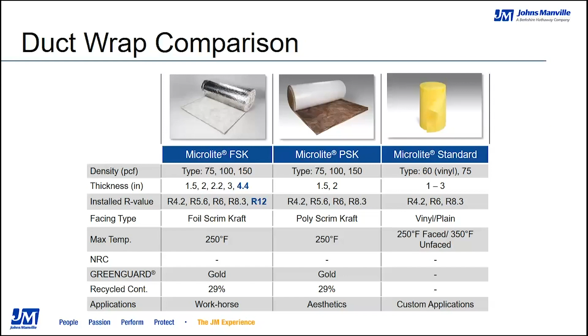So looking at duct wrap installation, the first thing I want to draw your attention to is over on the right-hand side of the screen, and just give you the components of actual duct wrap. This is an actual roll of Microlite FSK duct wrap, and you can see that the fiberglass is the white color there. The foil scrim kraft is the silver reinforcement. You can see the scrim pattern showing up on that duct wrap itself. And then you're going to have a factory-applied 2-inch staple flap that, when you're putting that duct wrap together, gives you the freedom to pull and wrap that around the duct and use your staples and seal that down as you're connecting the duct wrap together around the duct.